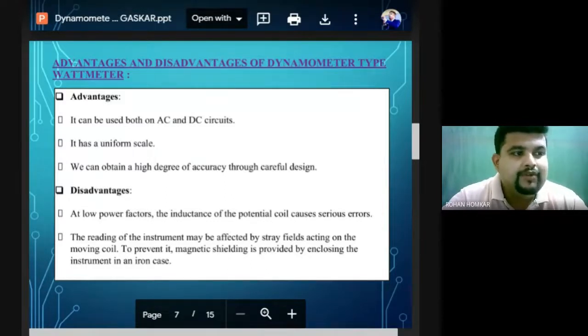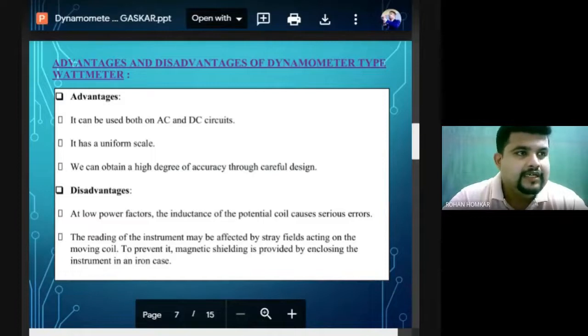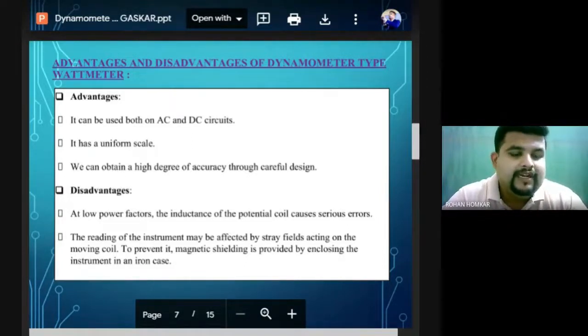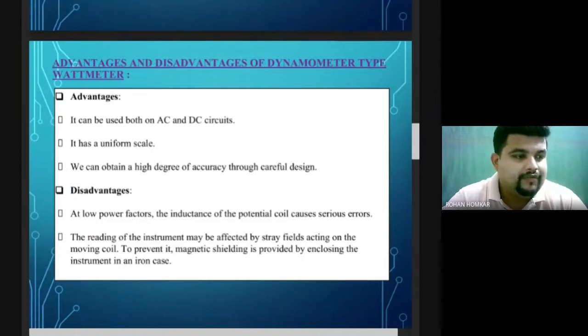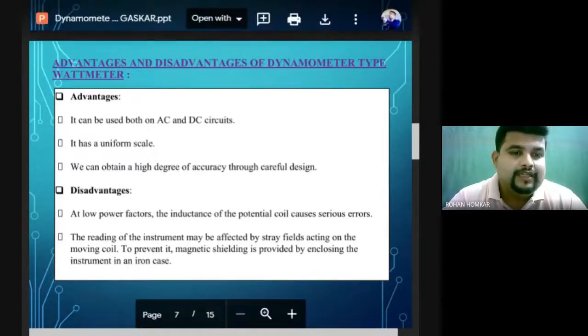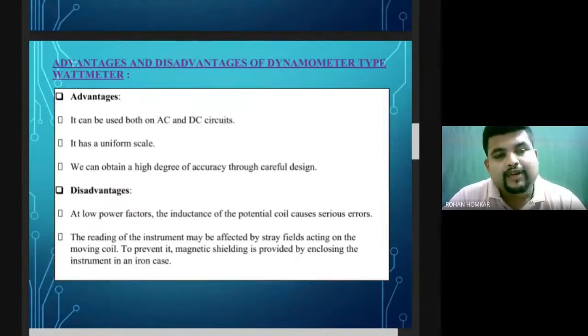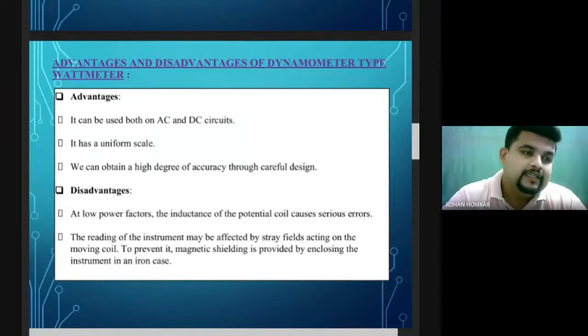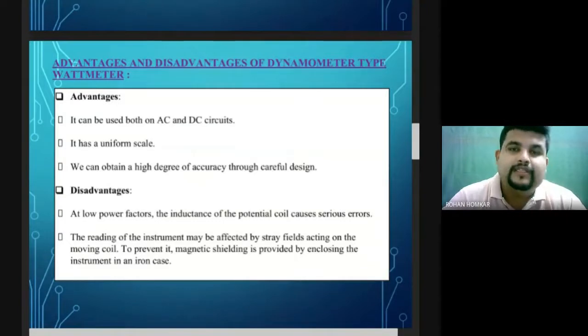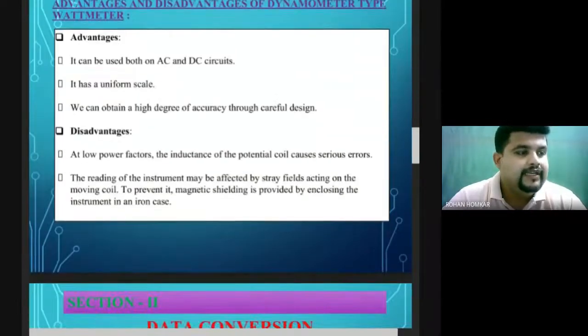Advantages of the dynamometer type instrument: it can be used on both AC and DC, it has a uniform scale, and we obtain a high degree of accuracy. Disadvantages: at low power factor, errors can occur. Also, the readings can be affected by stray magnetic fields — if a magnet is placed near the instrument, its magnetic field can interact with the instrument's field and cause incorrect readings.